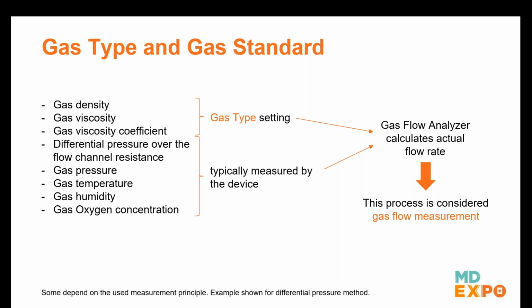The typical analyzer has a galvanic O2 sensor. Normally, those are good for about 2 years, depending upon how much oxygen they've been exposed to. But it's important that you calibrate it, and that if it is expired, you replace it, because it can change, right? If you set your analyzer to air and O2 auto, for example, where it uses the O2 sensor to tell you how much oxygen's in there instead of you telling it, now your gas type might not be accurate. So anytime you have a gas type or a gas standard that isn't correct, you're going to start getting measurement errors.